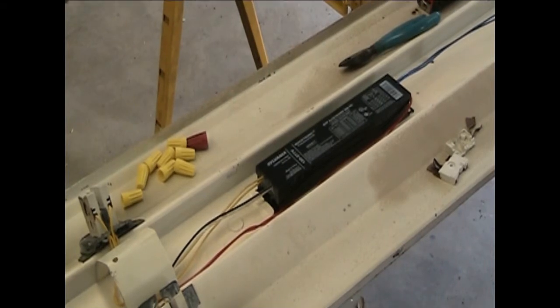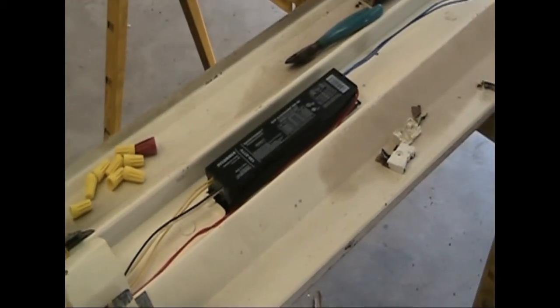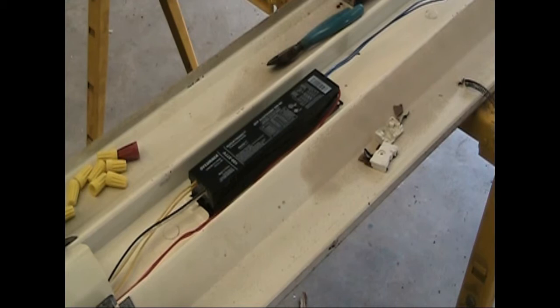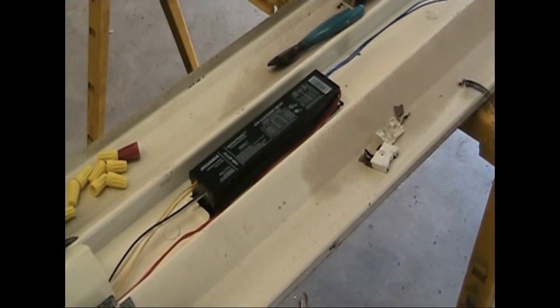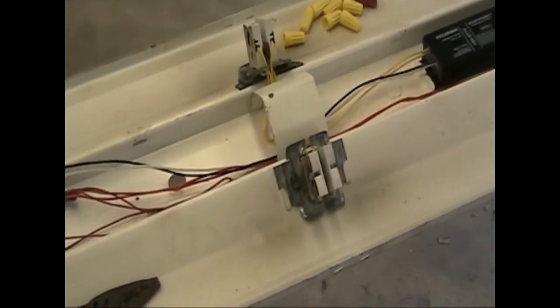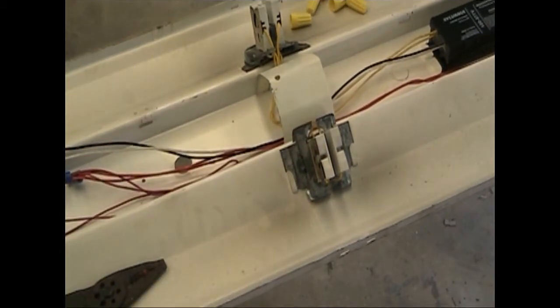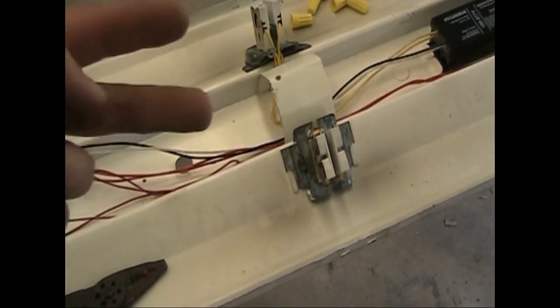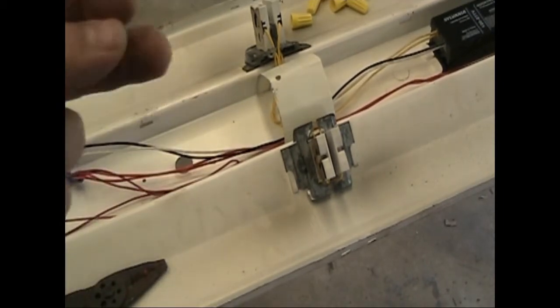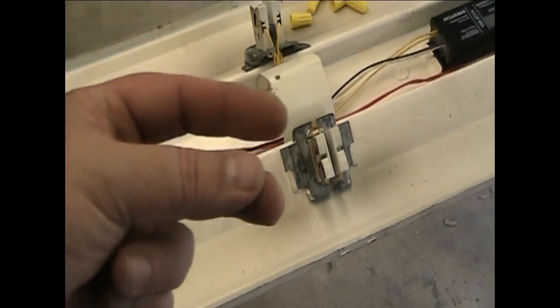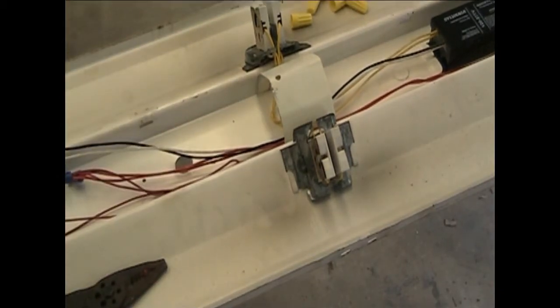I hope that helps you convert a T12 light fixture over to a T8. Nice thing about this is T12 and T8s both use the same exact receptacle. The distance between the pins is the same on a T8 as it is on a T12.